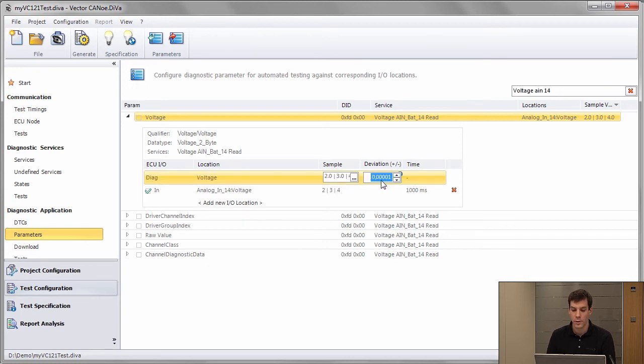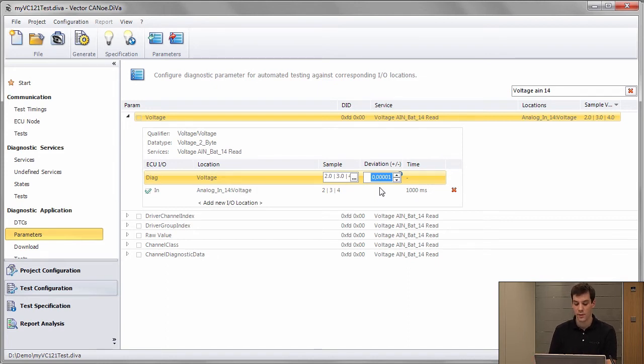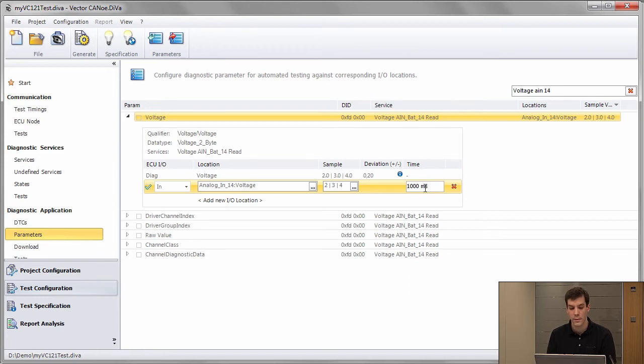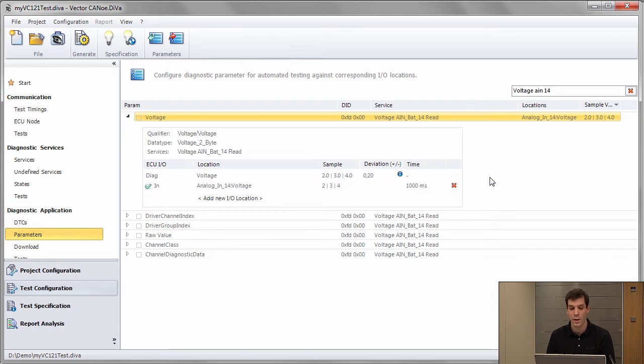I can also configure for cases where I have some measurement difficulties or I'm not very precise. So I can put a deviation in here — I put 0.2 volts here. I can also configure how much time it takes until the module should get the new value that is at the input. So I select one second here which should be enough for that.